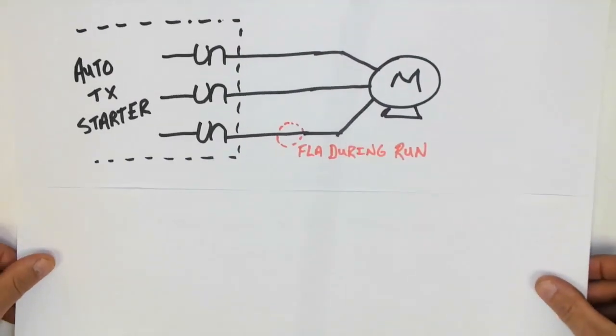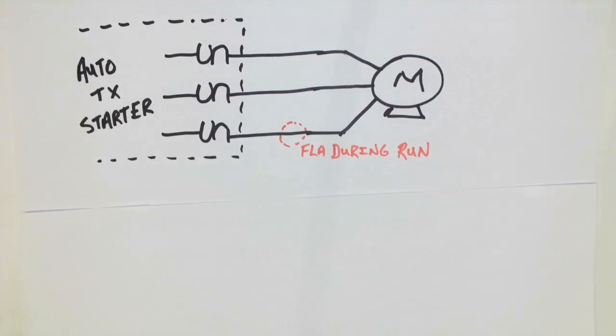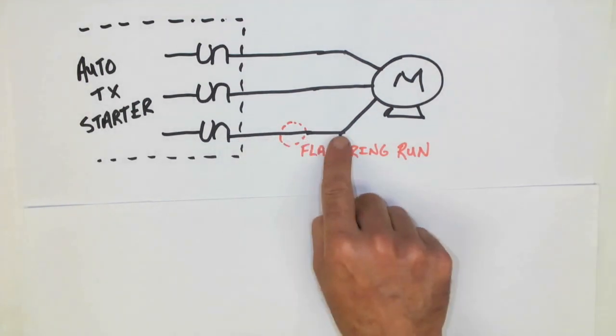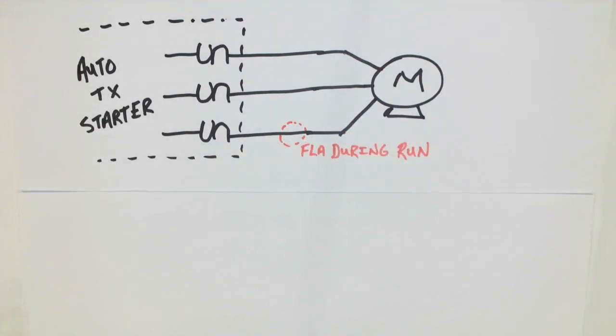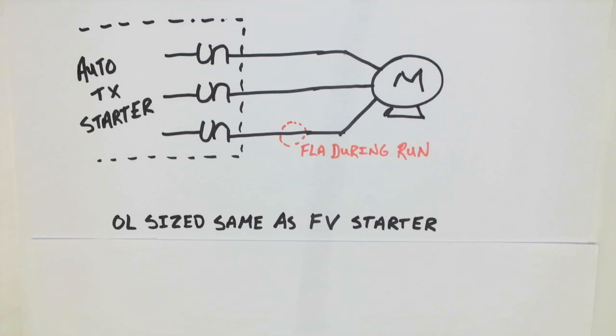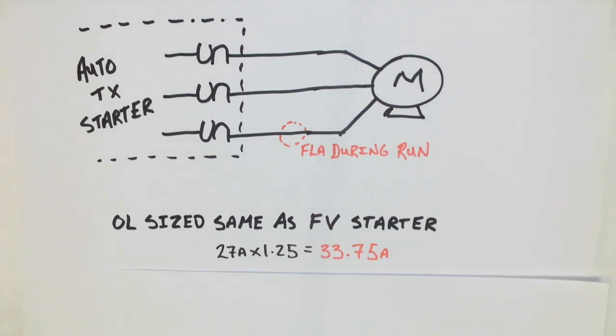Finally, what about the overloads? Remember that the overloads are always sized based on the value of current that will flow through them during run. On an autotransformer starter, there are only 3 overloads, and they are connected in the line conductors that supply the motor. This means that FLA will flow through them during run condition. This then results in the overloads being sized the same as a full voltage starter. And as we've seen before, that means we're taking the FLA, multiplying it by, in this case, 1.25 due to the service factor, giving us a maximum overload size of 33.75 amps.